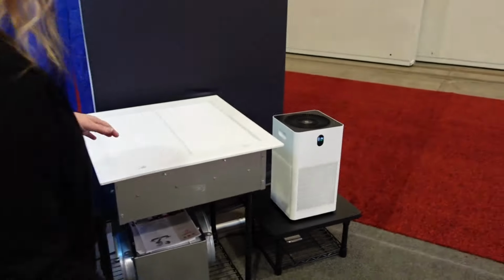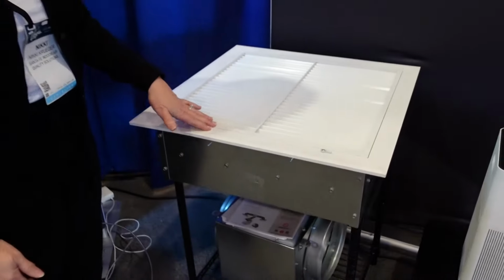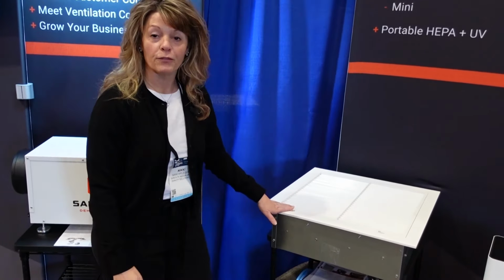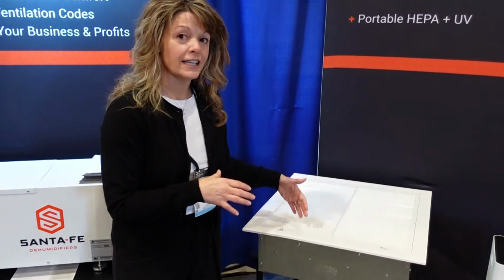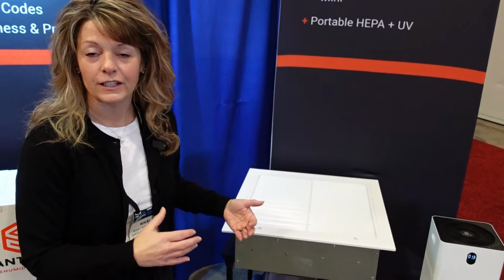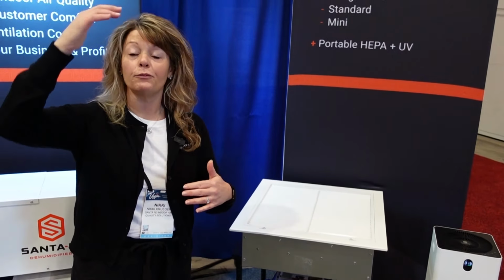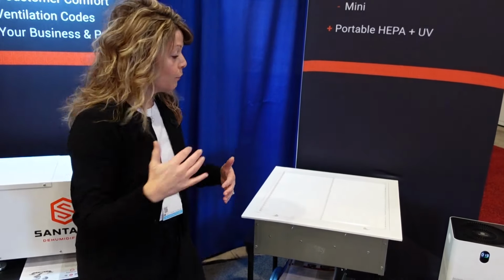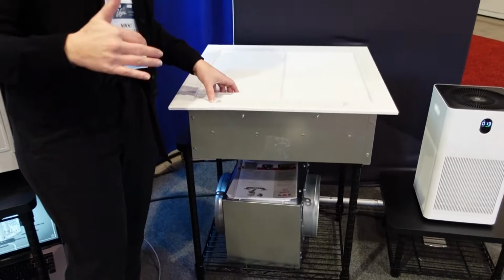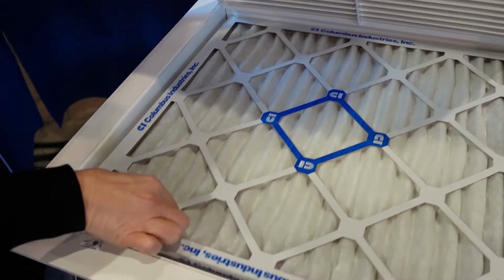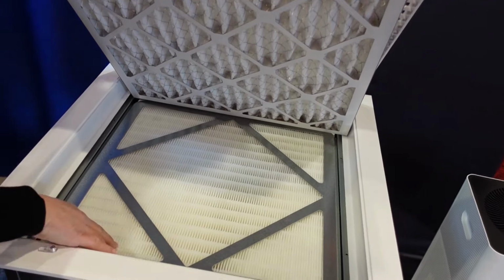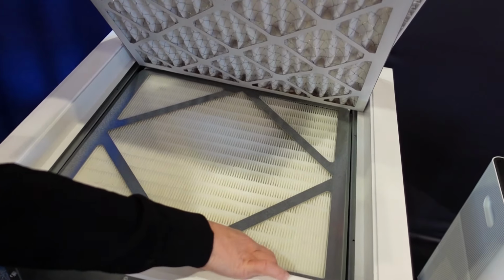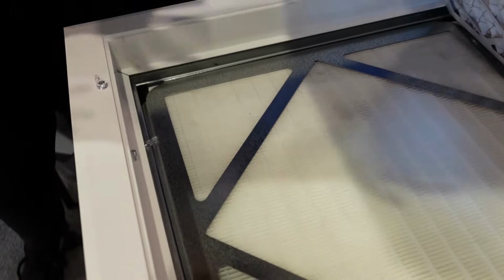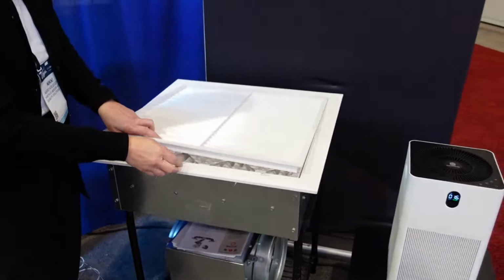It is a light commercial ceiling HEPA air purification system. What's really unique about this one is most of the ones on the market are designed for clean rooms, so they're a bit more expensive, and a lot of those are designed to be maintained from the top, meaning you have to go up into the ceiling to maintain it. What's unique about this one is it can be maintained from in the space. If I lift this up, you'll see a pre-filter, and then we've got the ceiling HEPA filter right here, with a little holder and tabs that can be pulled, so this unit is completely serviceable from inside the room.